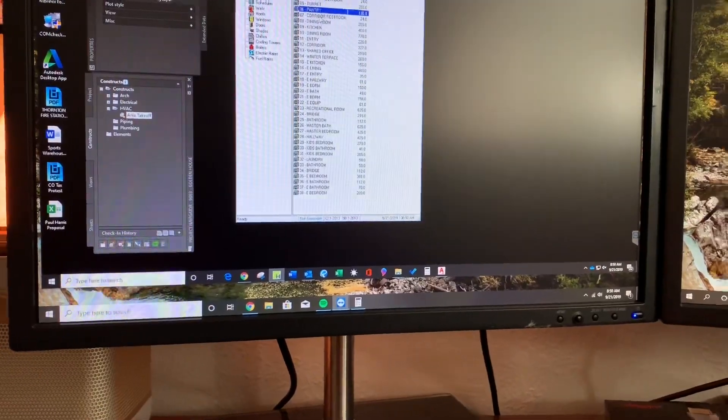And we'll go back in and add the R values. But right now you just get the geometry of the building put in. Your roof areas, wall areas, floor areas, window areas. You adjust your envelope properties. Basically I adjust it to the code minimum of the municipality for energy code. And then we'll go in and adjust the internal loads. That's people, lights, equipment. And scheduling of the timing when the lights and the people are in there. Typically residential design, two people per bedroom.